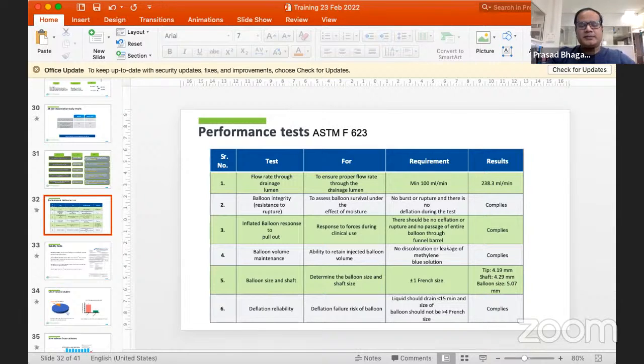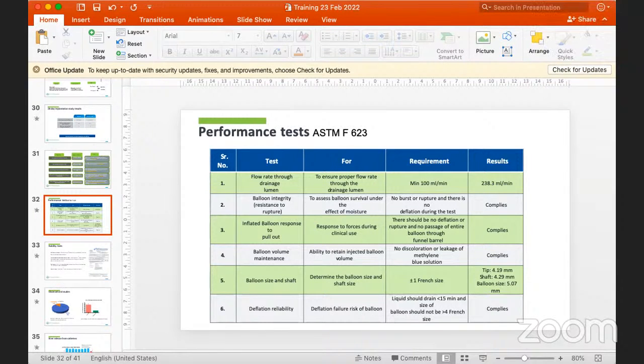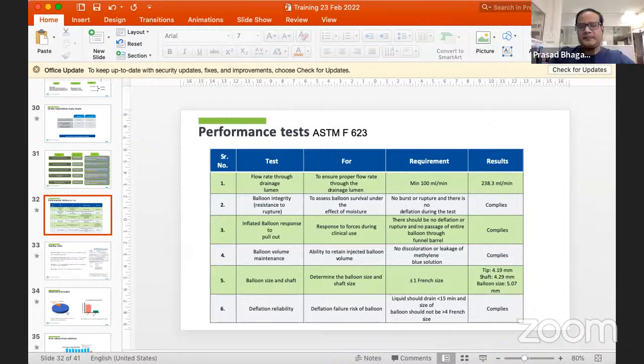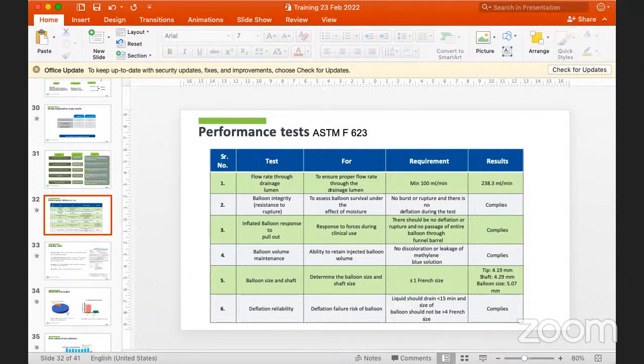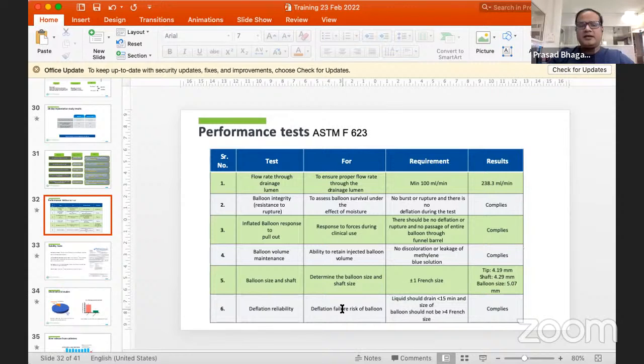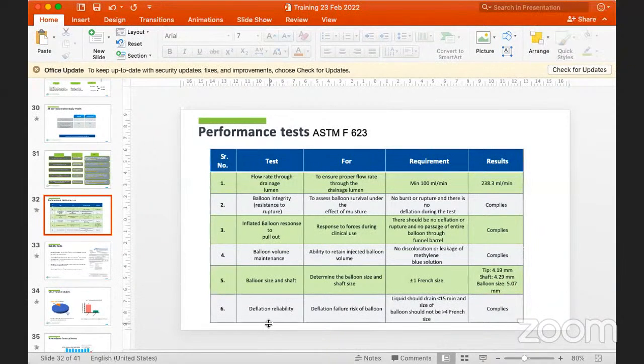As I've said earlier, the balloon is the most important part. Its integrity and its volume have to be maintained. If it doesn't maintain the required volume, it would be very small, and there are chances that it can damage the urethra, or if a simple jerk is given, it can come out also. We don't want that to happen. That's why it is essential that the balloon maintains its volume throughout the catheter use by the patient. The fifth test is balloon shaft and size. This also falls in the acceptable category. And the last important thing is deflation reliability.